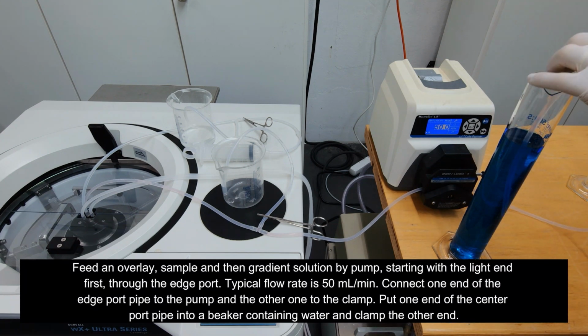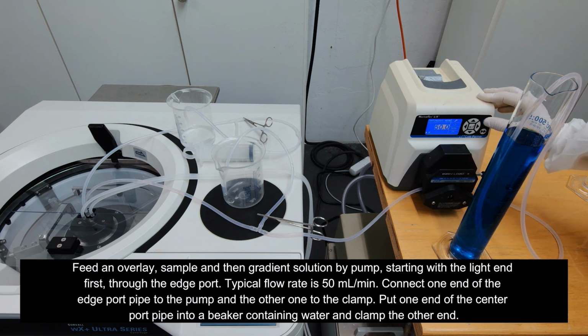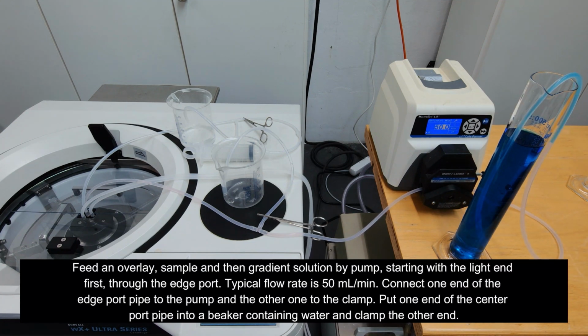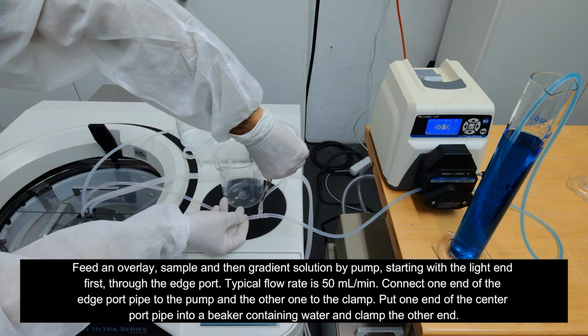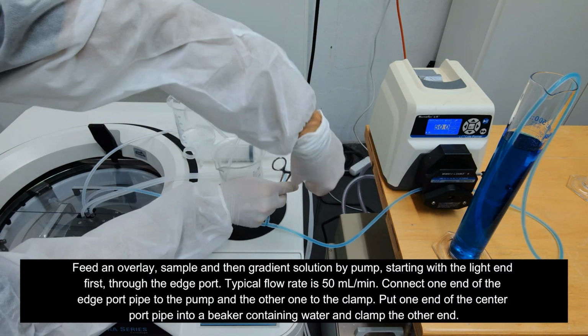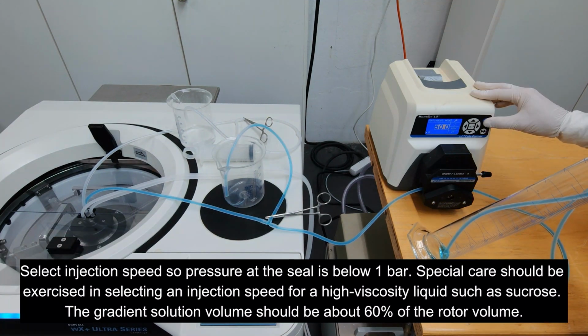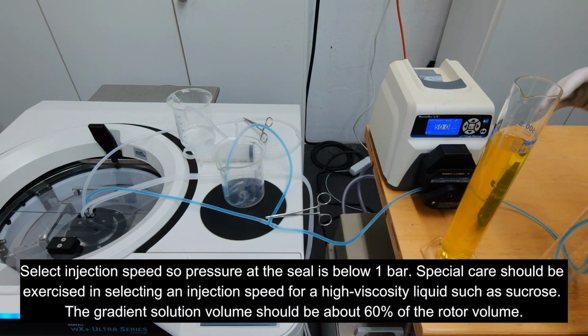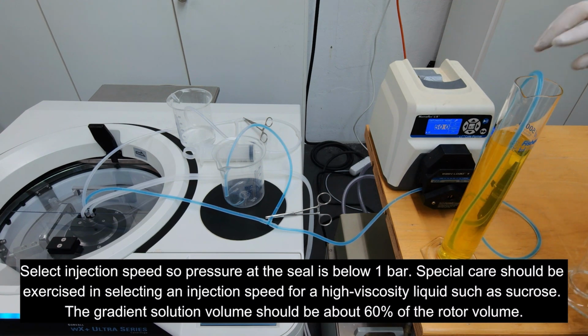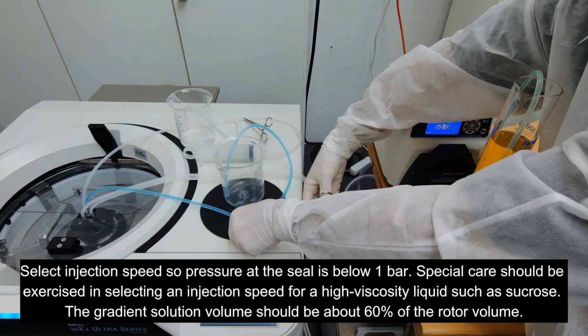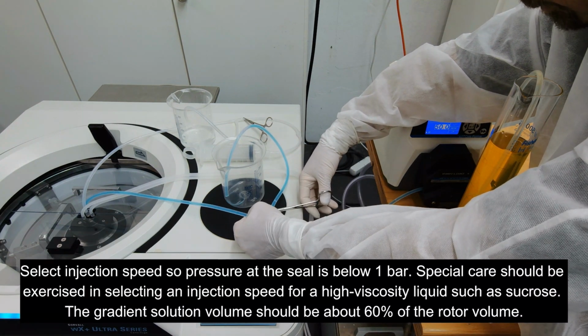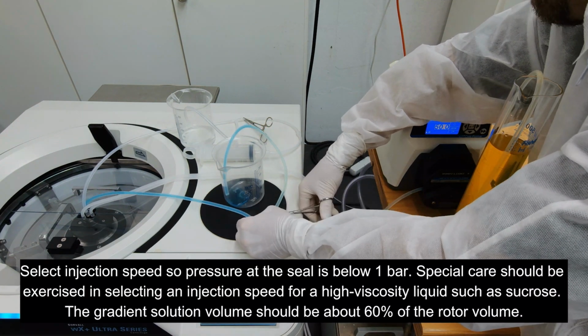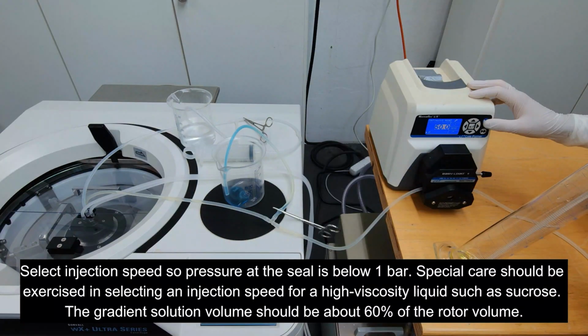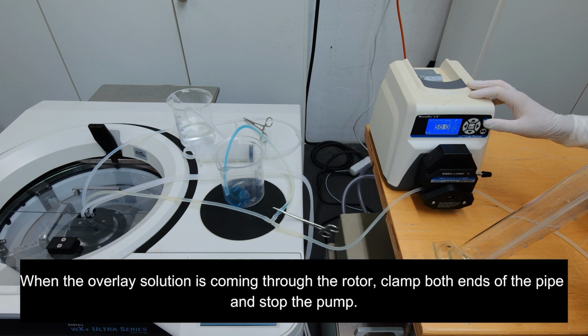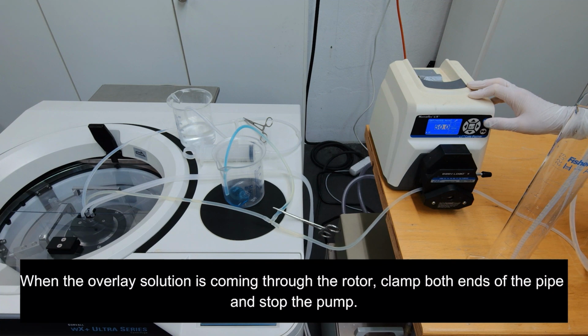Connect one end of the edge port pipe to the pump and the other one to the clamp. Put one end of the center port pipe into a beaker containing water and clamp the other end. Select injection speed so pressure at the seal is below 1 bar. Special care should be exercised in selecting an injection speed for a high viscosity liquid such as sucrose. The gradient solution volume should be about 60% of the rotor volume. When the overlay solution is coming through the rotor, clamp both ends of the pipe and stop the pump.